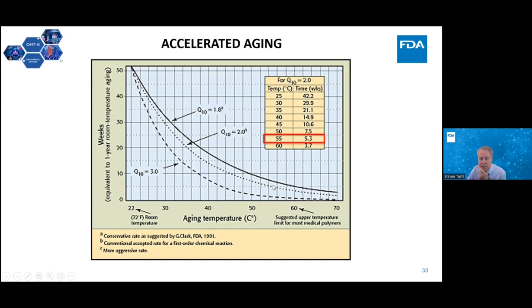If you scroll over, I'm going to switch to 55 degrees, that's the most common temperature that we see accelerated aging studies performed at. You can see that going up to the middle line in here, which is Q10 of 2, that dotted line, at 55 degrees, it drops off right at about 5 weeks, maybe a little bit above 5 weeks right here. And what I'm going to introduce you to is the calculations themselves.